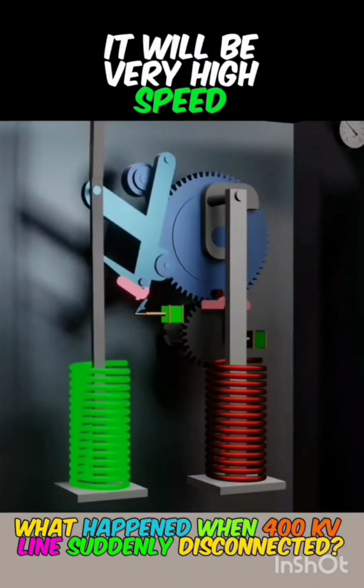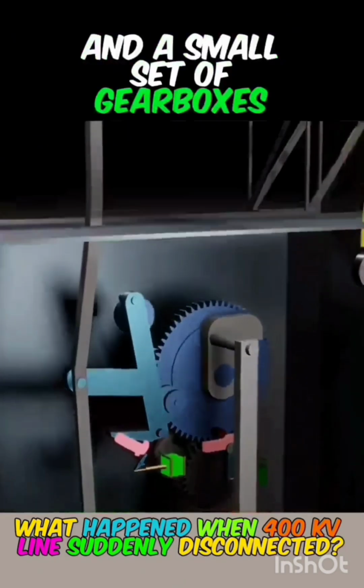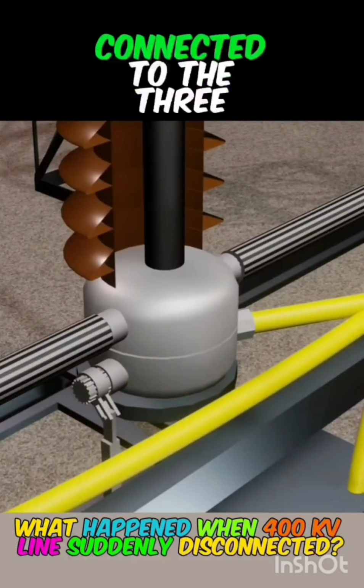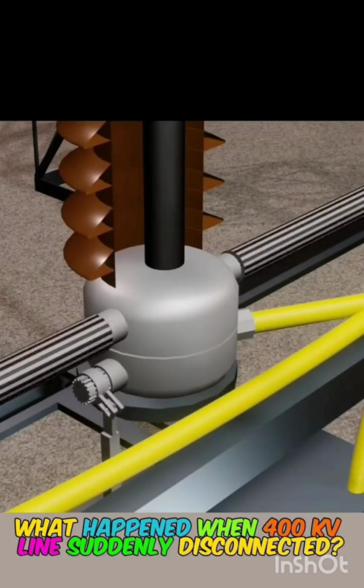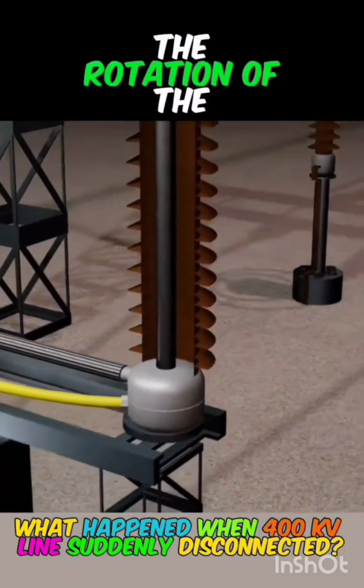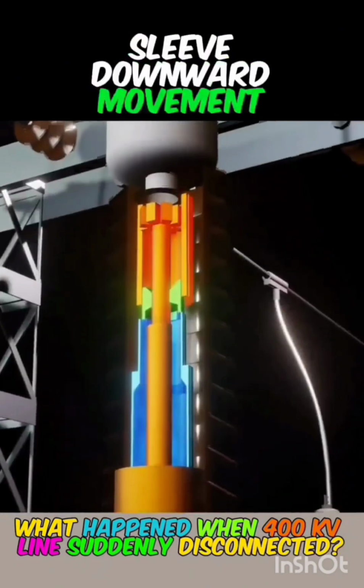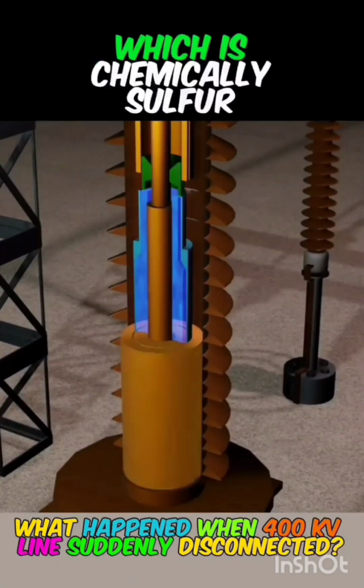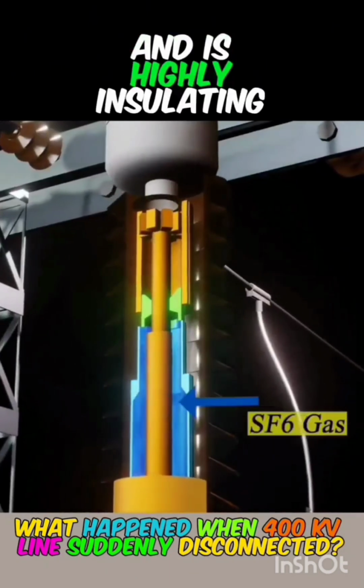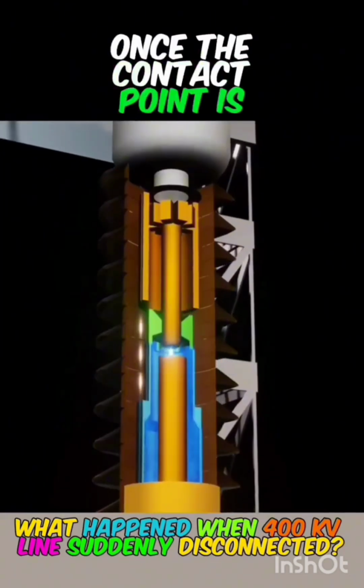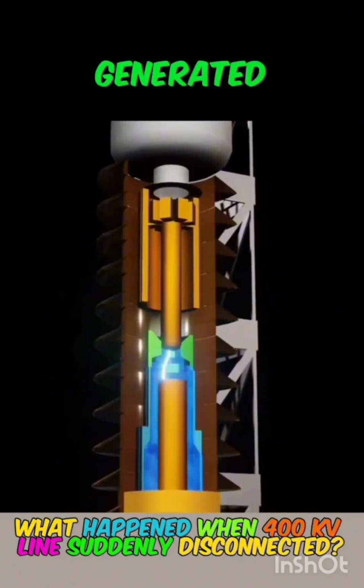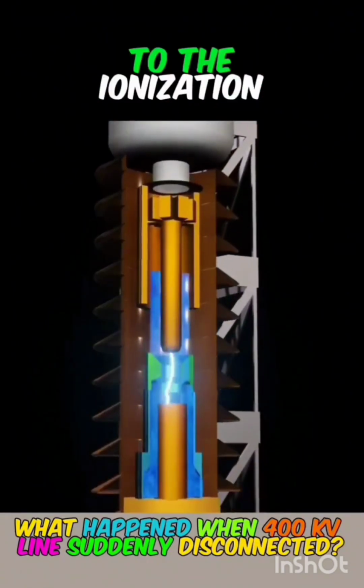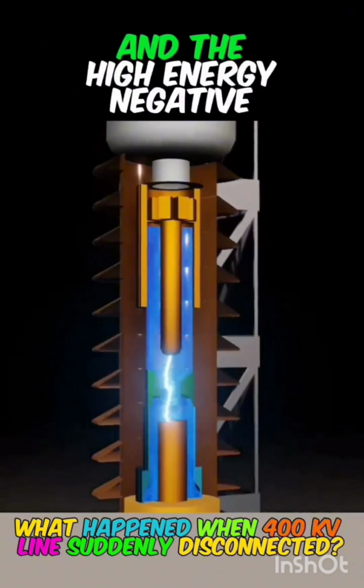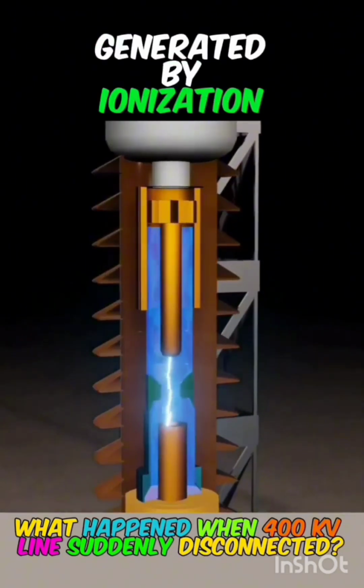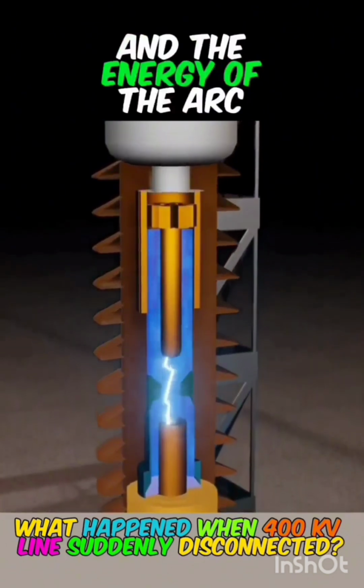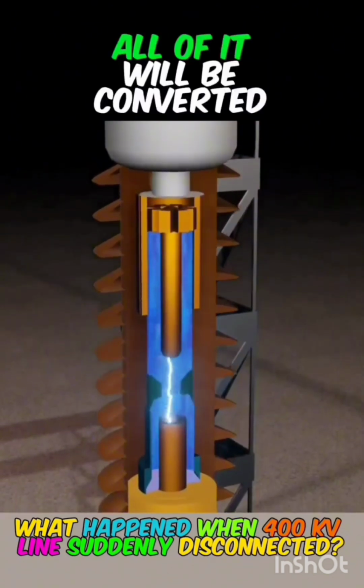and the spring below is no longer suppressed, it will push the pull rod downward at very high speed, and a small set of gearboxes connected above the tie rod is connected through a shaft to the three disconnecting sleeves like in the video. The tie rod can control its rotation. The rotation of the connecting shaft will make the copper sleeve move downward. This cylinder is filled with SF6 gas, which is chemically sulfur hexafluoride and is highly insulating and thermally stable. Once the contact point is separated, a huge electric arc will be generated, and the high temperature released by the arc will lead to the ionization of SF6 gas molecules, and the high energy negative ions generated by ionization will collide with the positive ions in the arc, and the energy of the arc will gradually disappear, and finally all of it will be converted into heat energy.